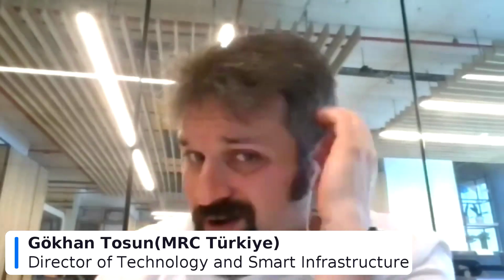So basically, the first question is about which of the options here are warning signs observed in your systems, especially in the dispatch center. Long distance reactive power transfer issues across major corridors, 500 kV corridors basically, can be one option. Heavy reliance on static shunt compensation, especially during export periods. Another potential issue is tap changers operating near their limits and very frequently. Another issue is voltage fluctuations during especially high solar generation hours.